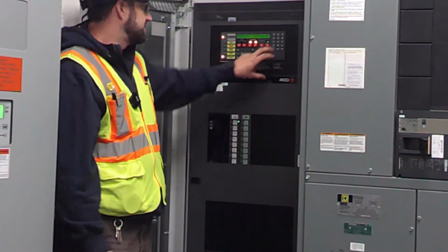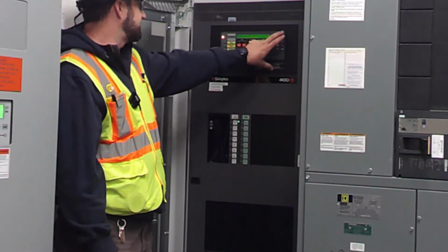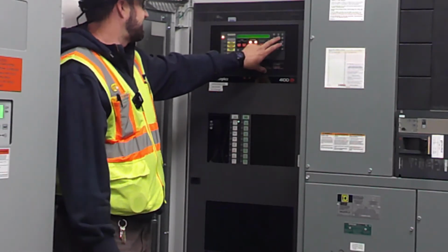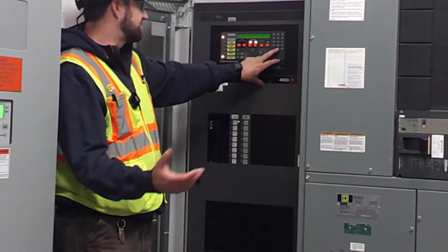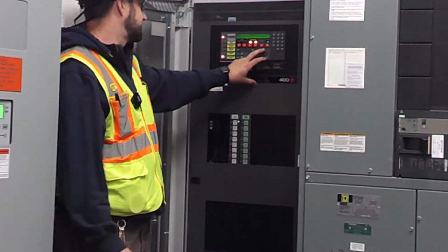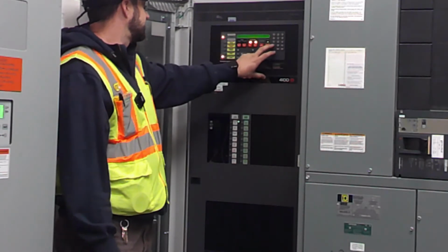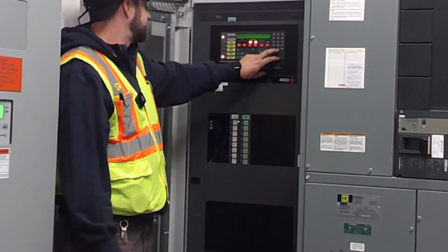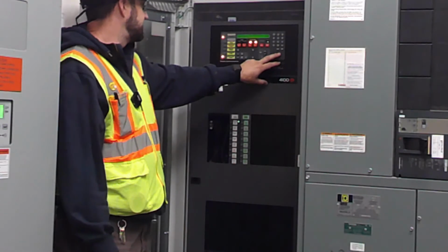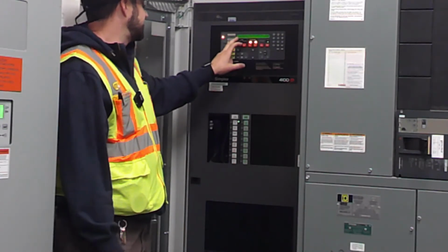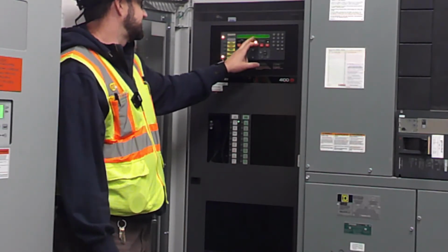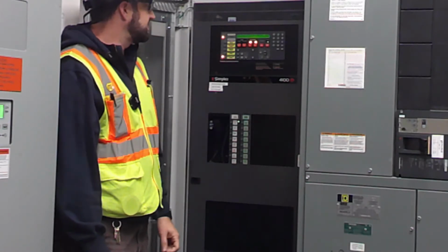It's as simple as hitting M3-5. That pulls up whatever address 5 is, and seeing there's nothing there for that, we'll try 10. So M310 is building E, first floor room. That's a DAS battery charge failure point.